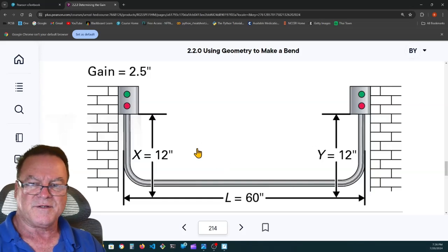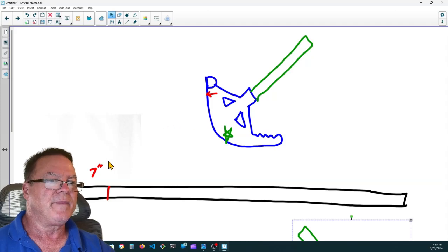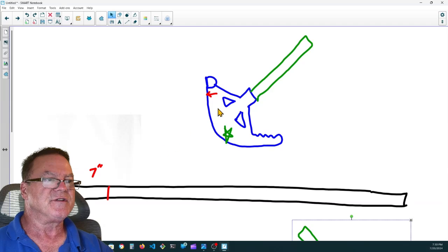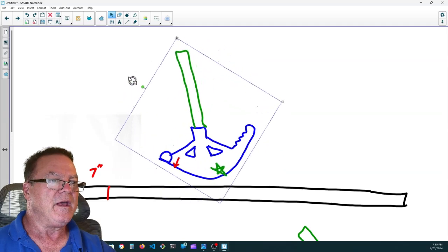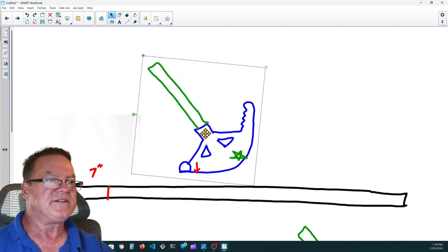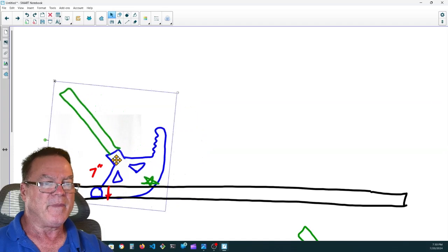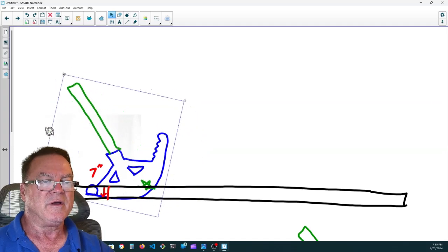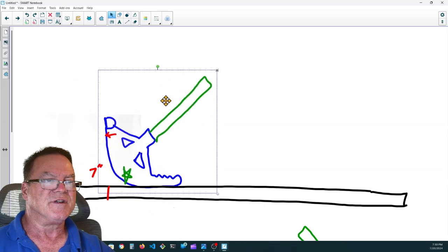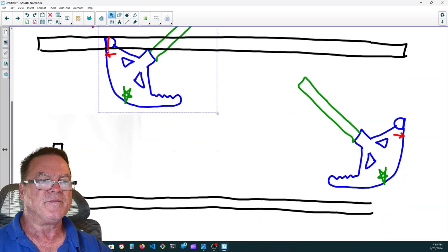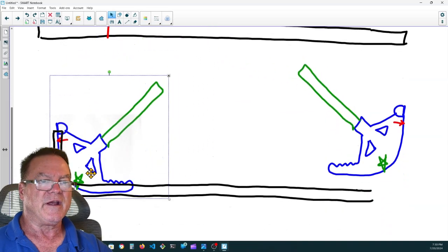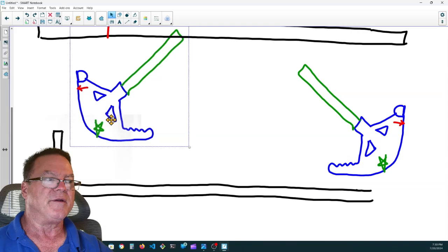Let's take a look at this. Okay, so we wanted a 12-inch stub. So we marked our conduit at 7 inches. That was 12 minus 5. And we'll take our bender and put it on our arrow facing the end we measured from, and we'll bend this up. We'll make ourselves a 12-inch stub. So here's our 12-inch stub. I know that's a lot smaller than my bender.